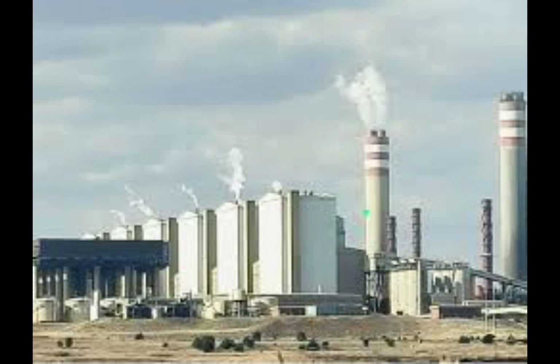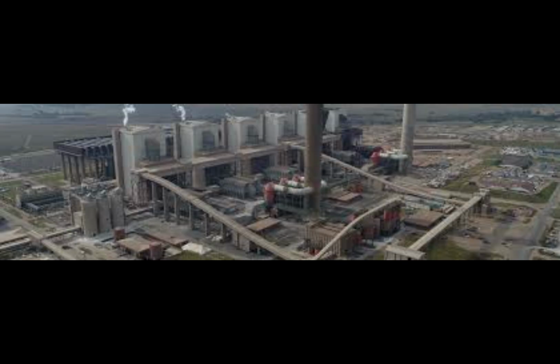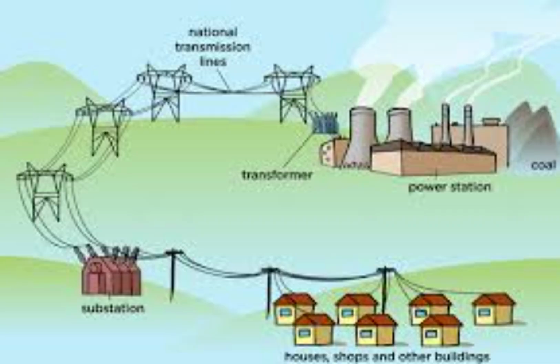Location. Located about 15 kilometers north of the existing Kendal Power Station near Witbank, Mpumalanga. Concept. Kusile Power Station is designed to consist of 6 800-megawatt coal-fired generating units for a total generating capacity of 4,800 megawatts. In 2023, the realistic sustainable output per unit was, however, projected to be some 350 megawatts. As of December 2023, Unit 5 was synchronized to the national grid. Following a 6-month period of testing and optimization, the unit's output will be commercially commissioned and bring total station output to 4,000 megawatts.